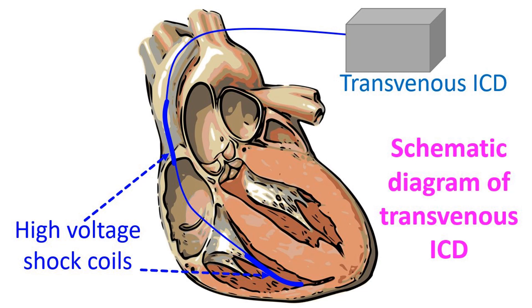The ICD system consists of a pulse generator with battery, usually implanted below the left clavicle for transvenous ICDs. The pulse generator is implanted below the left axilla in case of purely subcutaneous ICD and extravascular ICD. Left-sided implants are preferred because ICD shocks will be more effective with an ICD pulse generator CAN on the left side. The ICD pulse generator CAN is one active electrode, while high voltage coils located in the superior vena cava and right ventricle are the other active shock electrodes for a transvenous ICD.